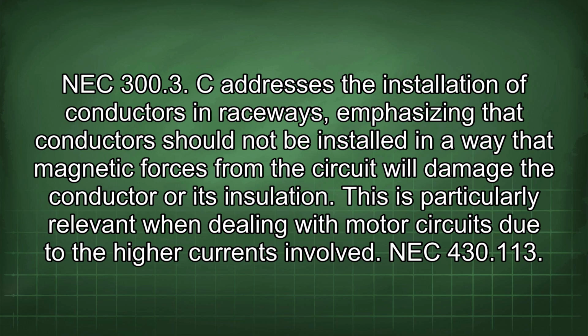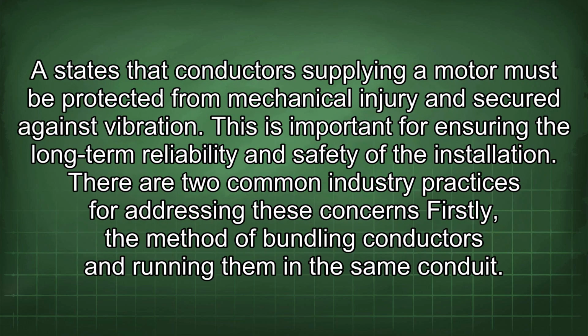NEC 430.113 states that conductors supplying a motor must be protected from mechanical injury and secured against vibration. This is important for ensuring the long-term reliability and safety of the installation. There are two common industry practices for addressing these concerns.